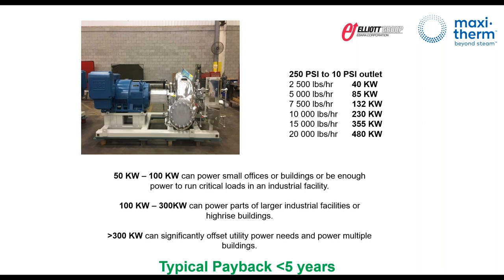And just for the attendees, rough numbers. First, we should stop designing, especially a new building, with a steam boiler typically rated for 150 PSI. I'm telling you, you should ask for 300 pounds rated and operate at 250 PSI or even a little bit higher, go through a turbine, and then distribute your steam. I think that's the way to go. It's almost free power. To give you another number, as a rule of thumb, 5,000 pounds per hour means about 5 million BTU. So if you have an average load of 5 million BTU all year round, you can generate 85 kW with a 5 year payback.